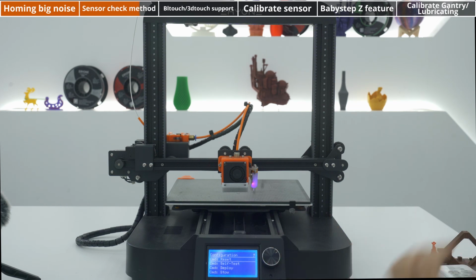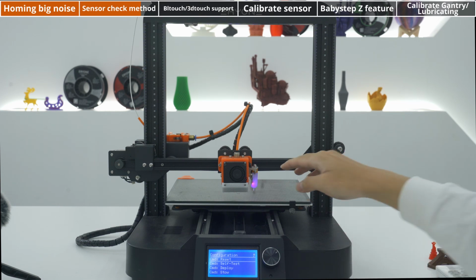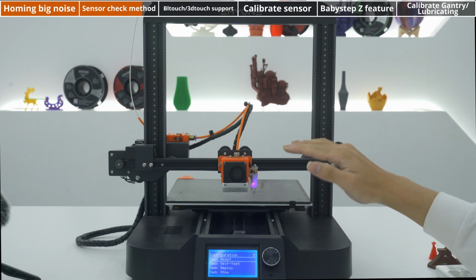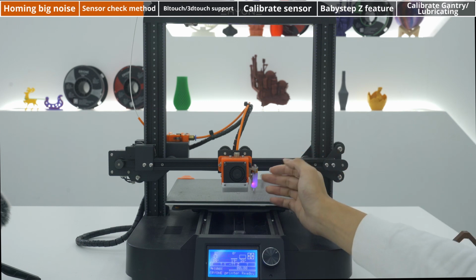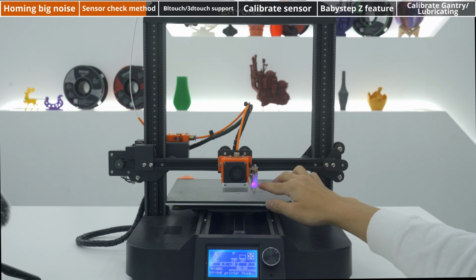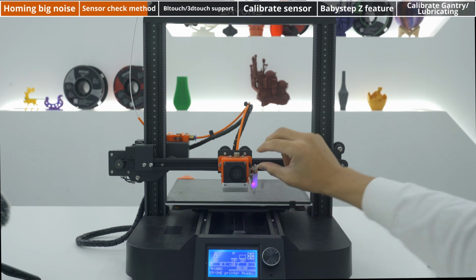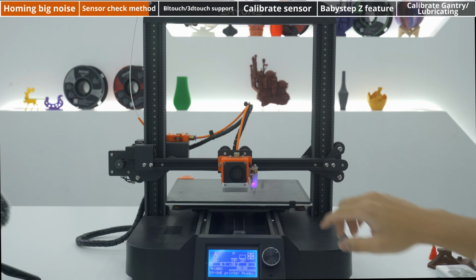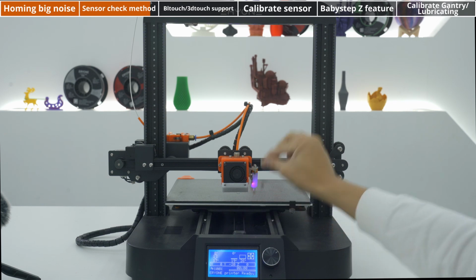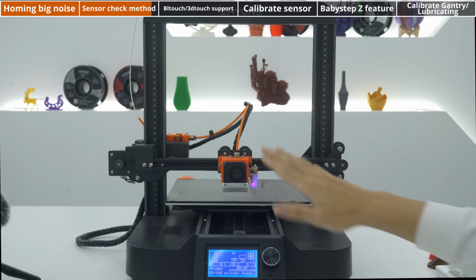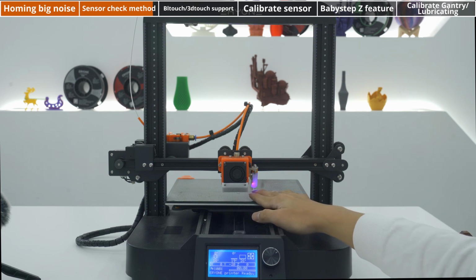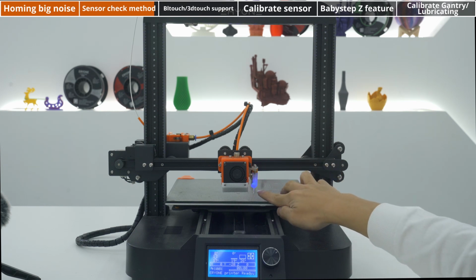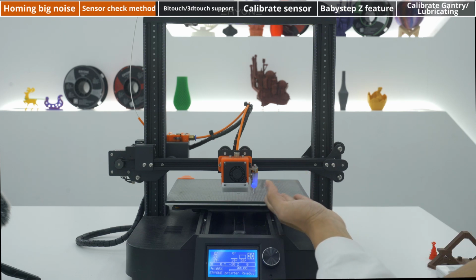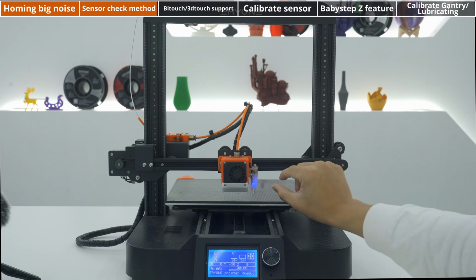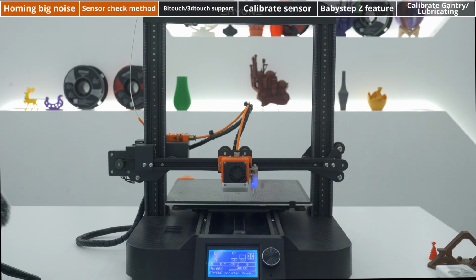Okay. So if on this test the sensor doesn't raise up or drop, it means maybe the cable is not all tight. Maybe one of the pins is loose. So try to disassemble this part and check that all of the cable is tight enough. And on the other side, if just this pin can't go up and drop, try to check whether the pin is bent or not. If you find the pin is bent and it can't come through this hole, then you need to use your finger to straighten it a bit, then it can work again.